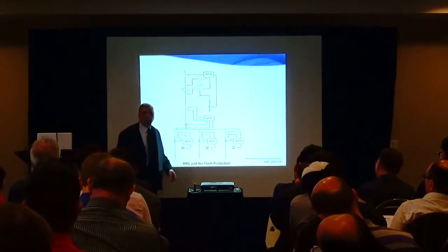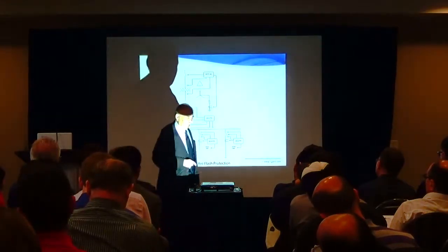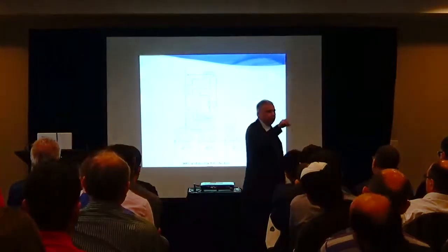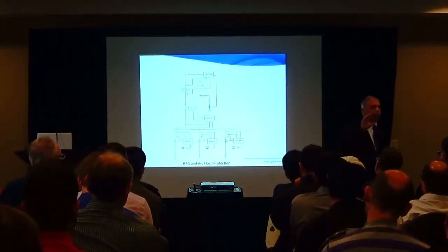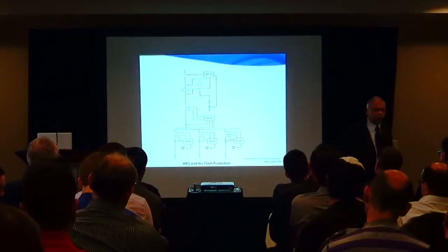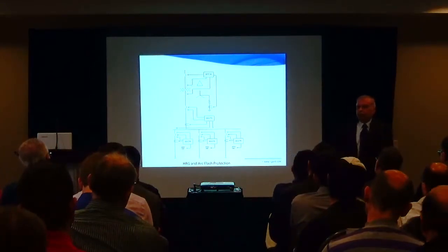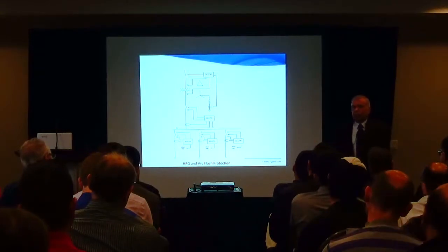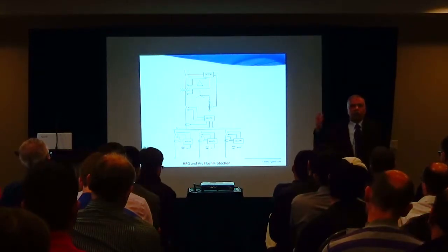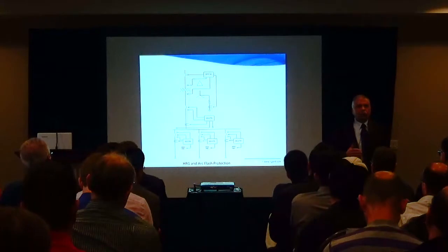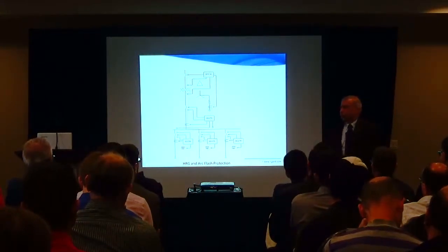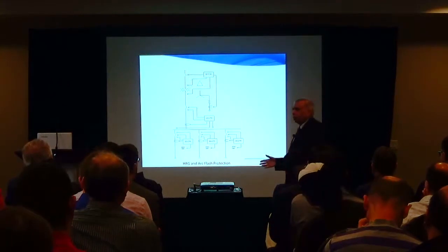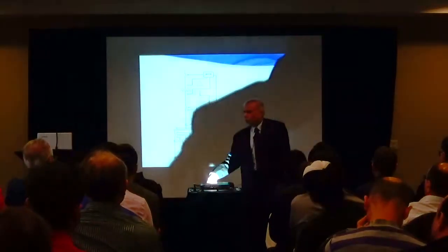So in arc flash studies, you will often find that they have red marked these situations where they are exceeding 40 calories, because there is no PPE available beyond 40, right? Which means there's 150 calories or 250 calories. Have you seen any of these arc flash studies? Yes. So now the question is, are you going to address it or are you going to ignore it and put it in the file cabinet?